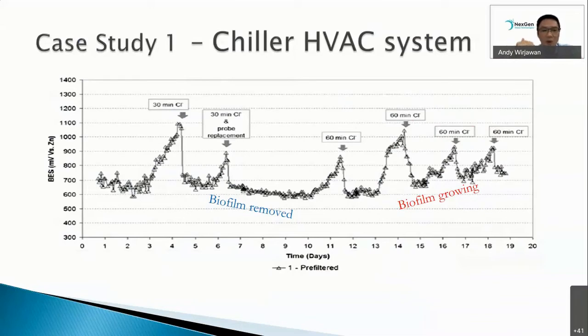And then on the fourth day, as we can monitor, once the biofilm has built up significantly, the operator institutes a shock dosing of chemicals. Once the shock dosing, which in this case is chlorine, is done, the biofilm is removed and the reading drops down again. And then it is maintained by the continuous dose. But by the fifth or sixth day, it starts to build up again.